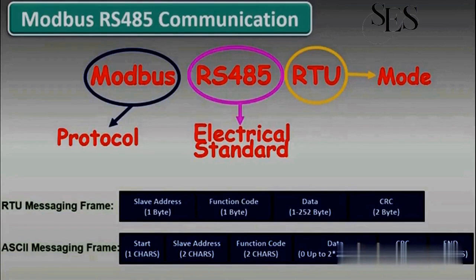Modbus RTU is the most common way of Modbus protocol implementation because it takes half a time from Modbus ASCII to transmit the same content. These two modes are incompatible, so a device configured for RTU cannot communicate with one using an ASCII.